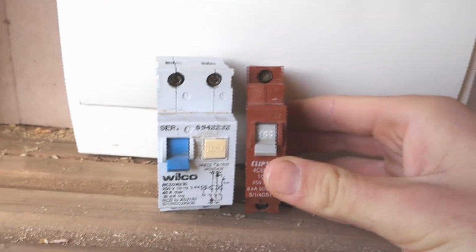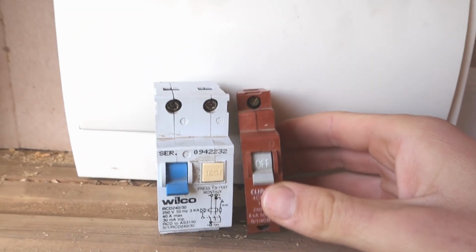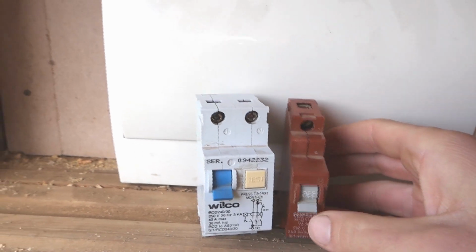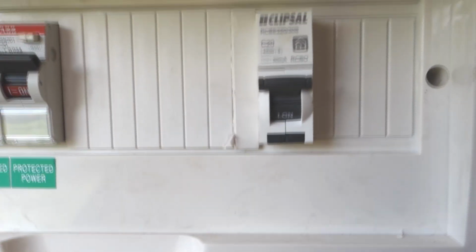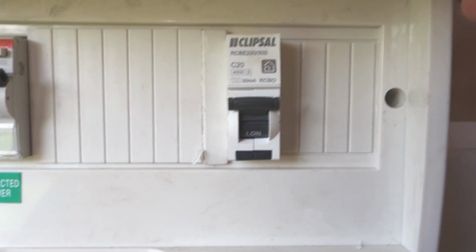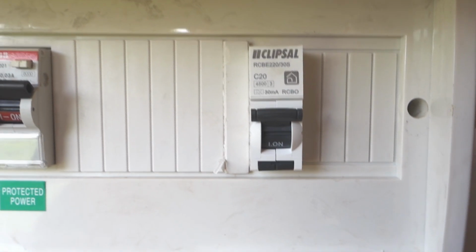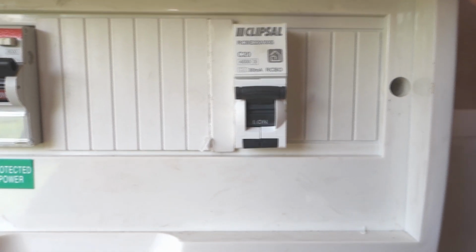If we had a power circuit and the power circuit was causing a fault, that safety switch will trip, and it's also going to take power out of the lighting, so it can leave you in the dark a bit. So we much prefer the individual ones because if that trips, it's only going to take out what it's protecting. So if we go back to the power circuit, it's just going to be the power circuit.